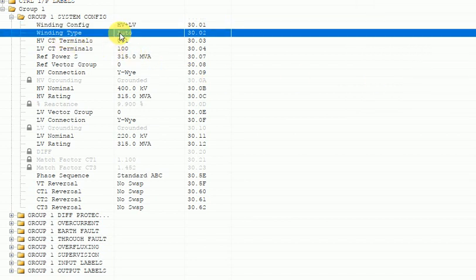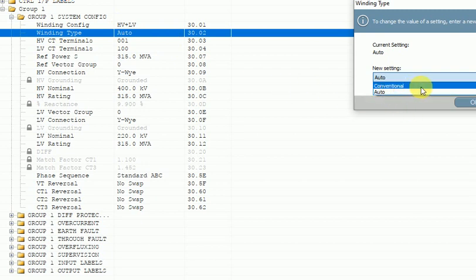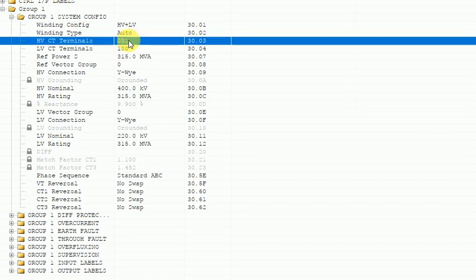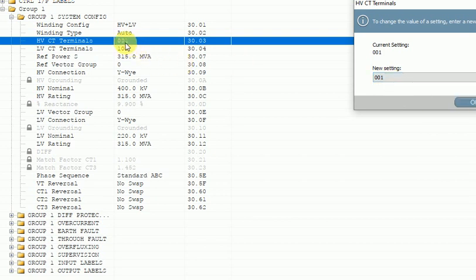For winding type — whether it is an auto transformer or conventional transformer — in my case it is an auto transformer, so I will select auto. For HV CT terminal and LV CT terminal, these two parameters are very important. HV CT terminal means my HV side winding. If you click, there are two options: 001 and 011. I am using 001 because I am using only one CT on the HV side.